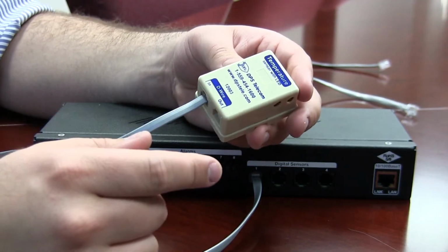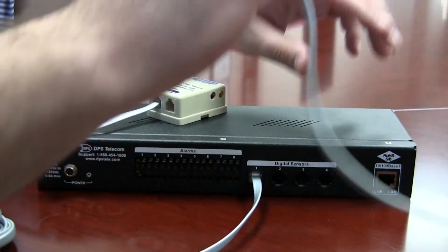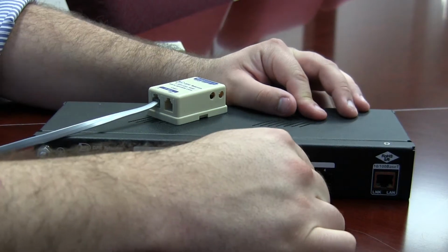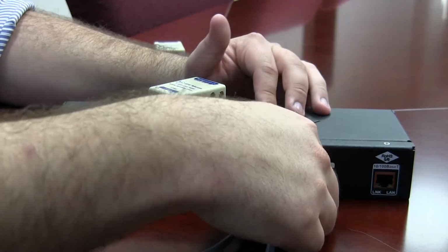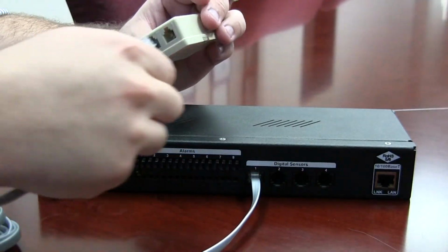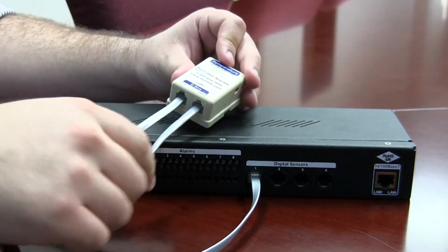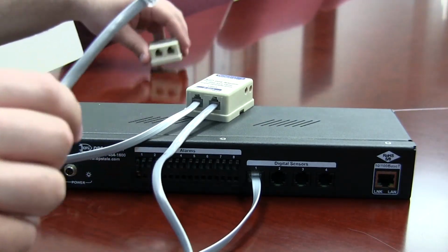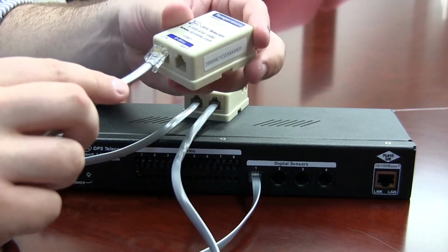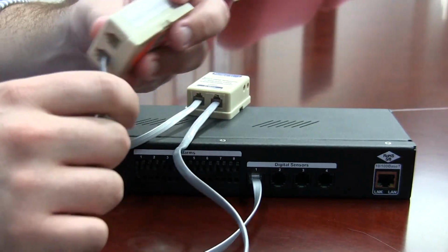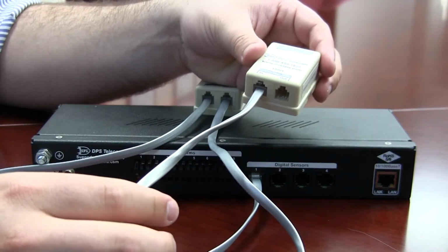If you want to add additional sensors, you can always use the other ports and start up to four total daisy chains. But the real advantage comes in when you can simply connect to the out of your first sensor and then wire into one more sensor. And now you've developed a string and you don't have to home run every one of the sensors.